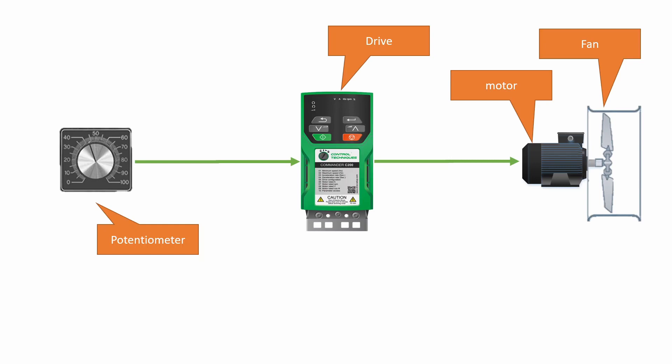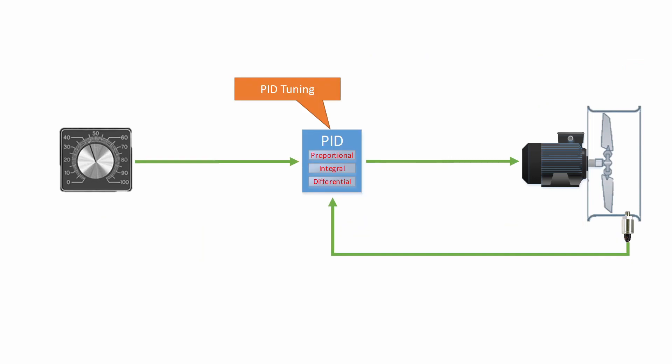Let's say that's not what we want to do. Let's say we want to maintain a pressure on the output side of the fan. To do that, we added a pressure transducer, and then we connect the pressure transducer to the drive. Inside the drive, there is a PID. The PID is a proportional, integral, and differential controller.